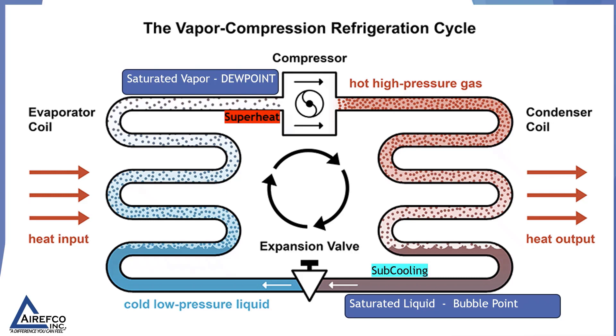Looking at the refrigeration cycle, as our refrigerant enters the evaporator as a liquid and absorbs heat, it evaporates and becomes a saturated vapor at the exit — this is where we measure superheat. On the PT chart, we use the dew point column to calculate superheat coming out of the evaporator. On the high-pressure side, gas enters the condenser and condenses into a liquid at the end of the condenser.